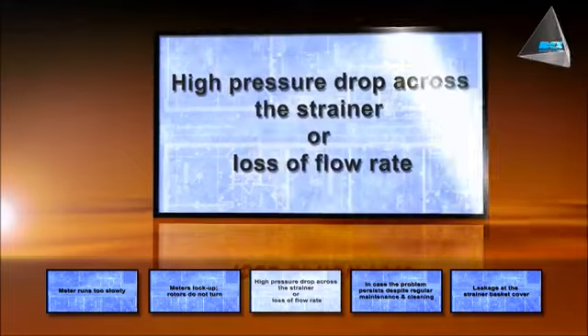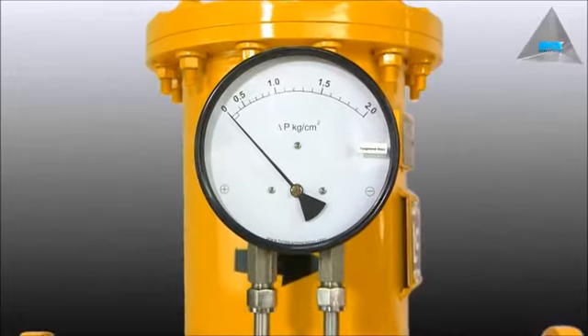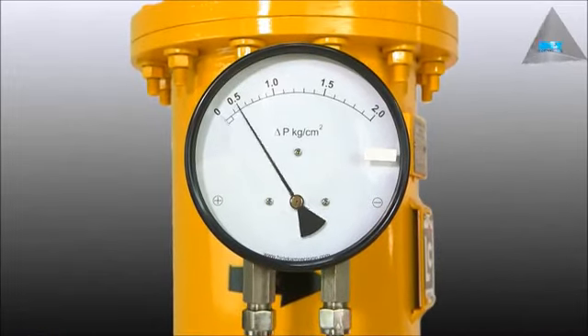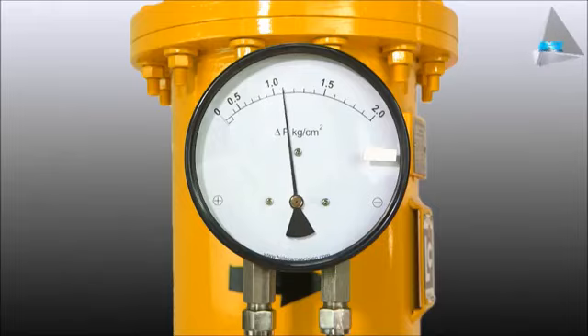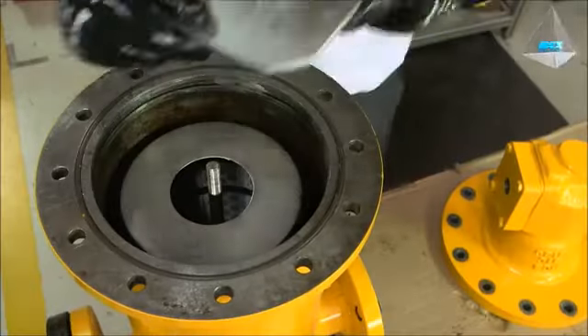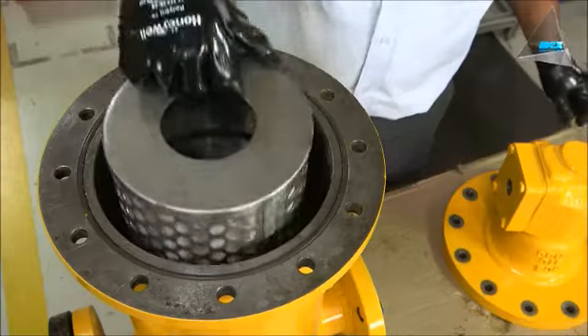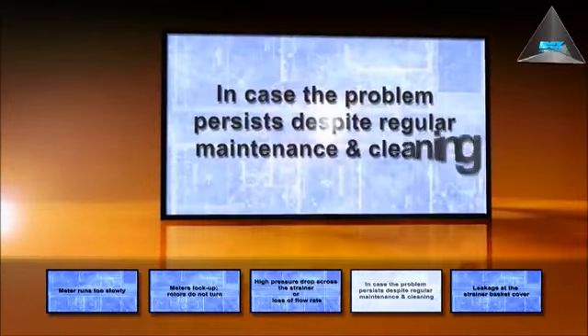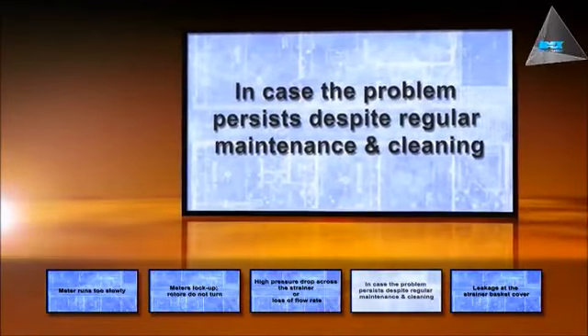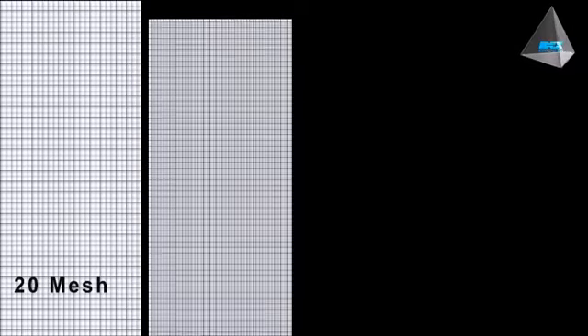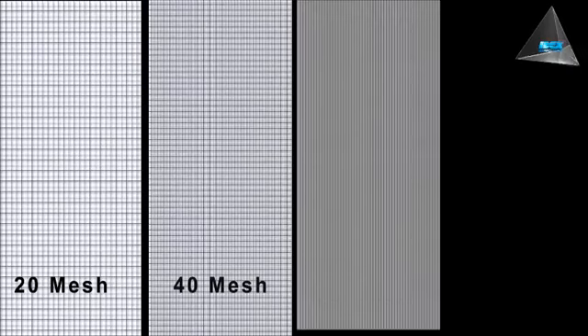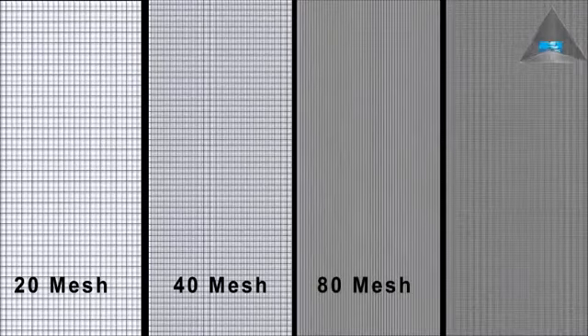internals. High pressure drop across the strainer or loss of flow rate. Possible cause: the strainer basket is partially clogged by foreign particles or dried material. Solution: clean or replace the strainer basket. In case the problem persists despite regular maintenance and cleaning. Solution: inner mesh may not be correctly sized for the product. Therefore, replace with a mesh appropriate for the product viscosity.